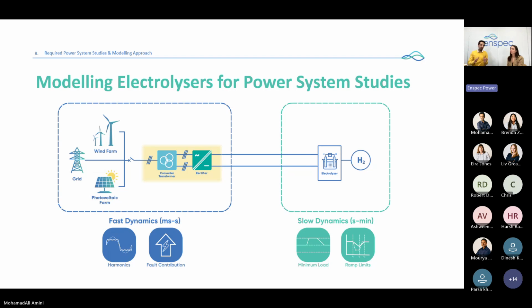The first layer will introduce fast dynamics, in the range of milliseconds to seconds, while the second layer will introduce slower dynamics, in the range of seconds to minutes. In addition, the first layer will define harmonic and fault contribution at the point of connection, while the second layer will introduce limits to the model, for example the minimum load limit or the ramp limit, as I mentioned previously.